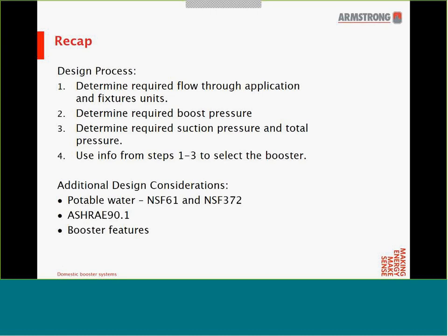To recap, the design process is as follows. First, determine the flow — found by figuring out the application, the number of fixtures, and the fixture types. Second, determine the boost pressure using the different components of the boost pressure calculation. Third, determine the required suction pressure and total pressure. We use this information to select our booster. Once selected, we need to consider other factors such as NSF 61, NSF 372, ASHRAE 90.1, and any important booster features.